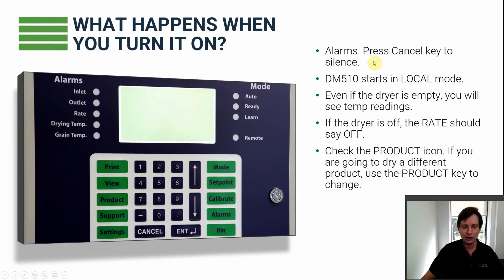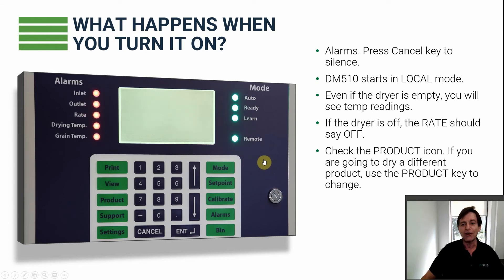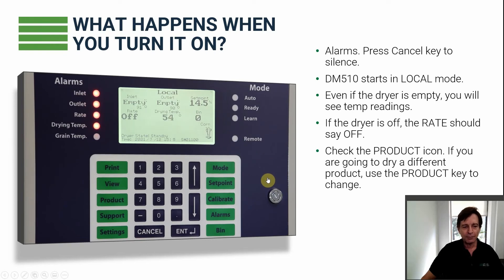Everything's wired up and commissioned — we're ready to go for the first time. You turn on the power at the bottom, the screen lights up, and it takes about a minute to load the software. The lights will go through a sequence of testing. We're going to get some alarms because the dryer is not running at the moment. We cancel those, and now we've started up: the dryer is not running, both sensors read empty, the dryer rate reads off, and the drying temperature will take a little time to get up to ambient.